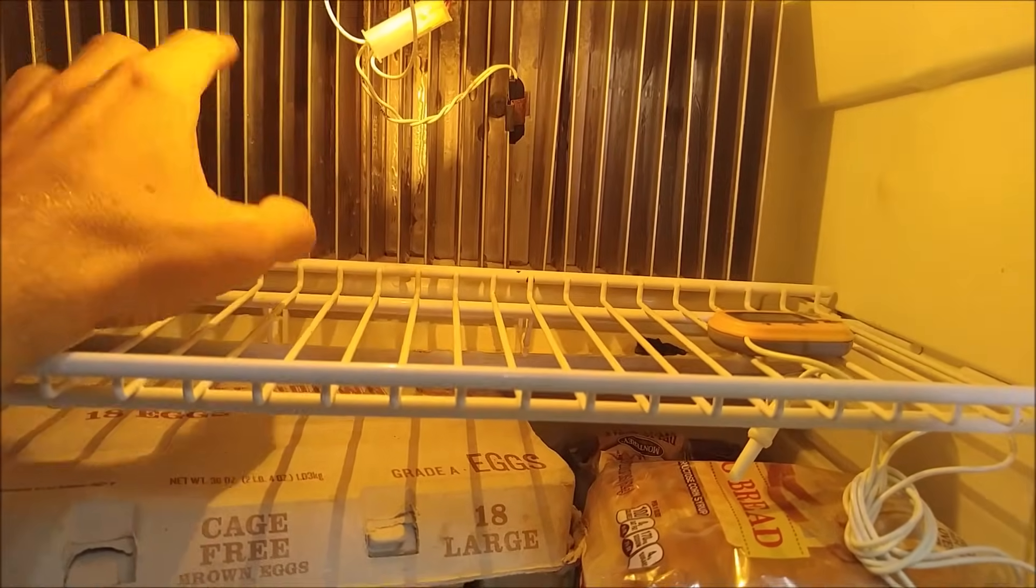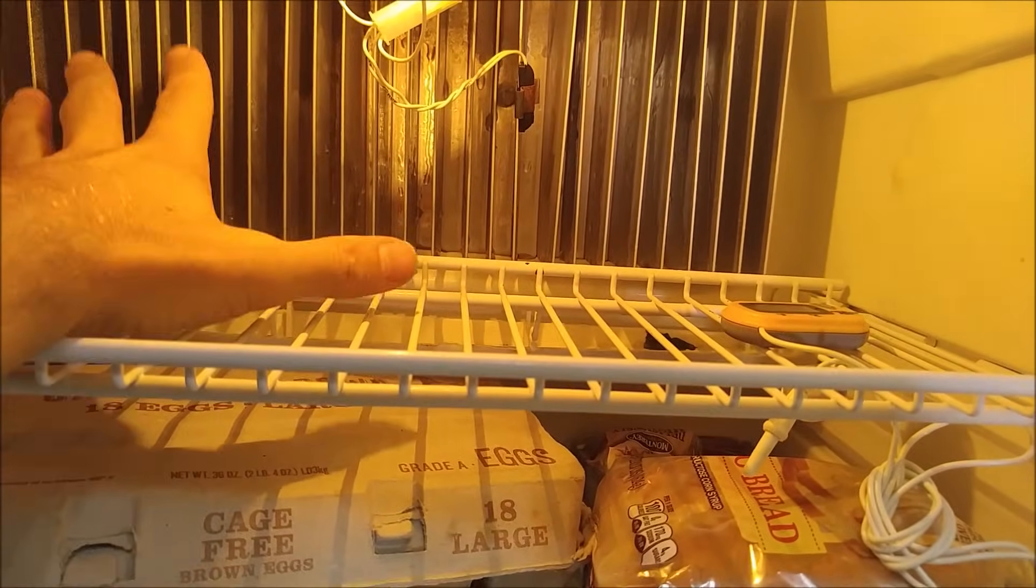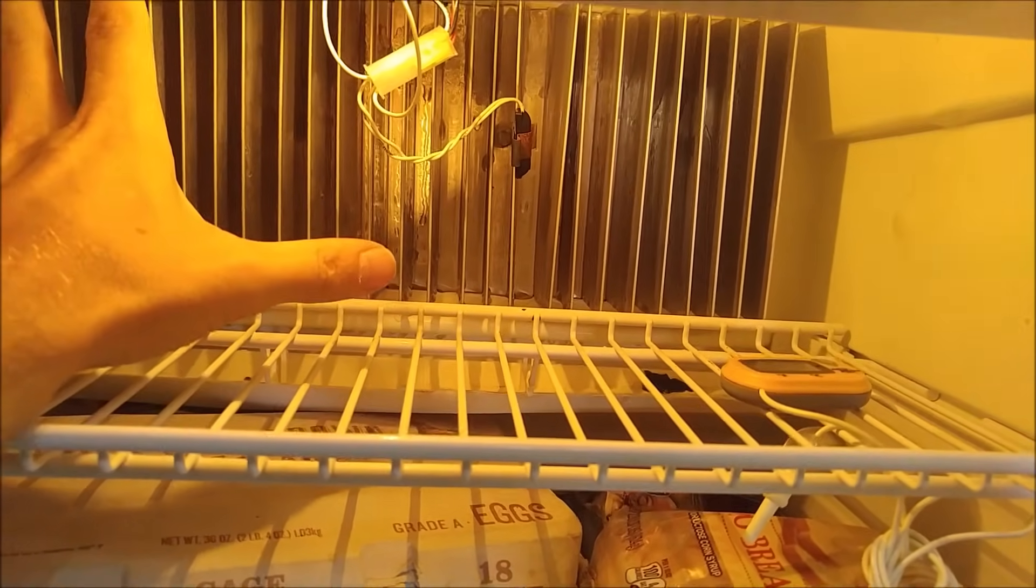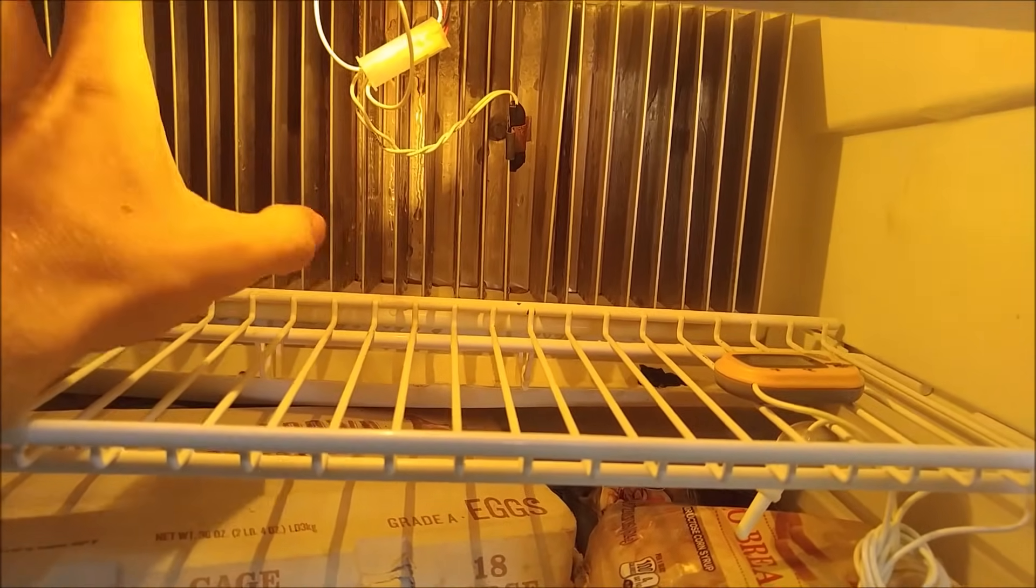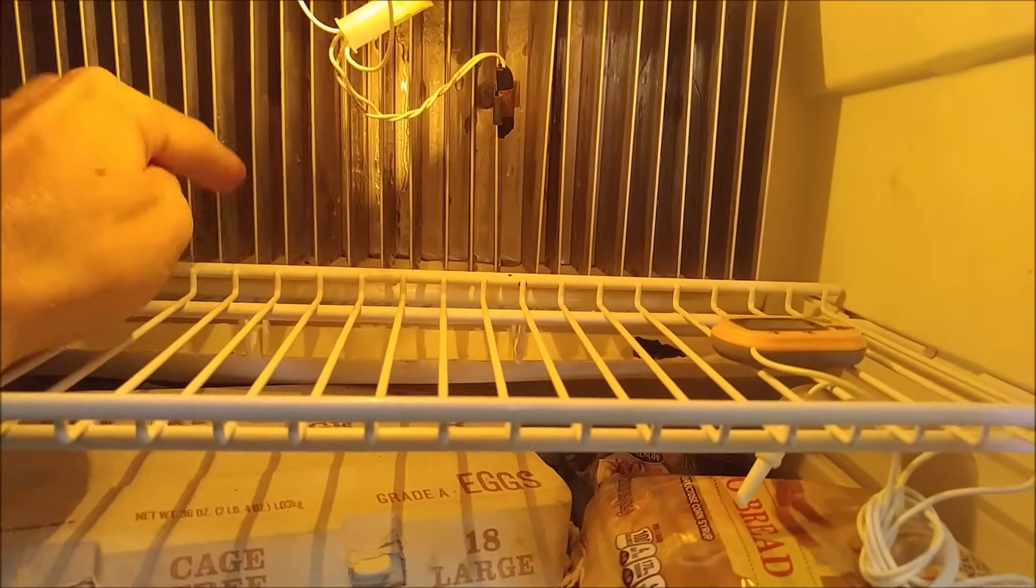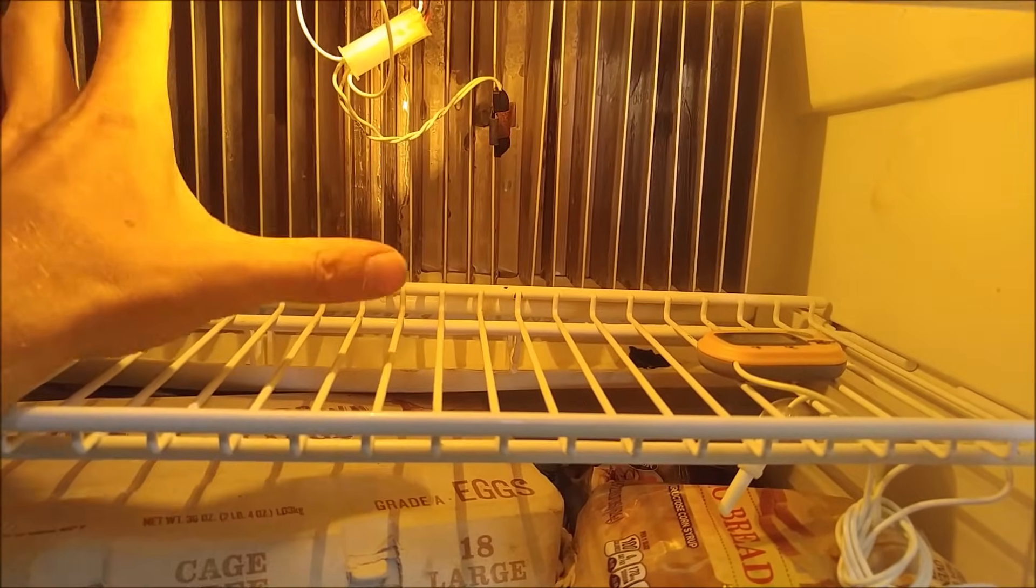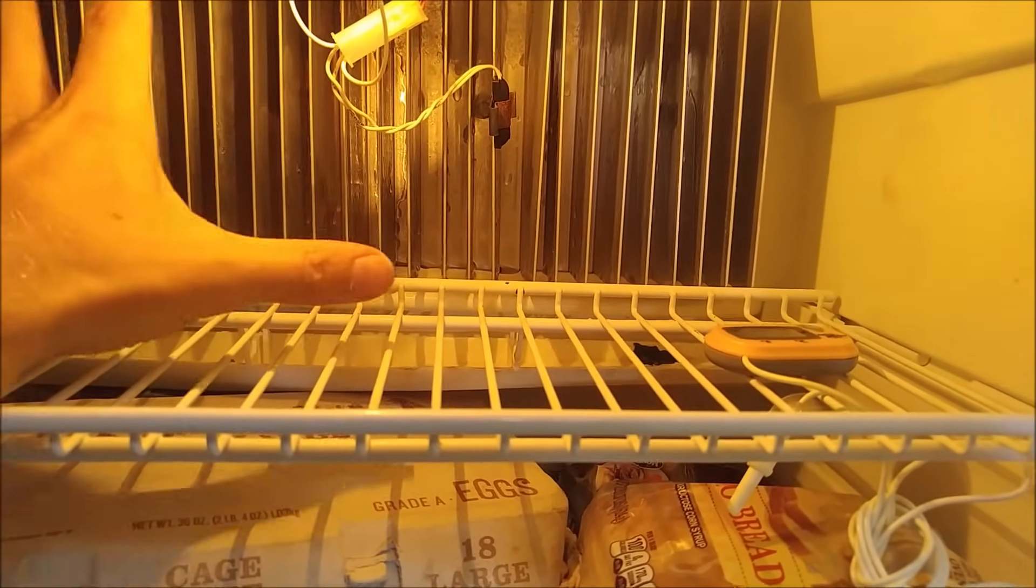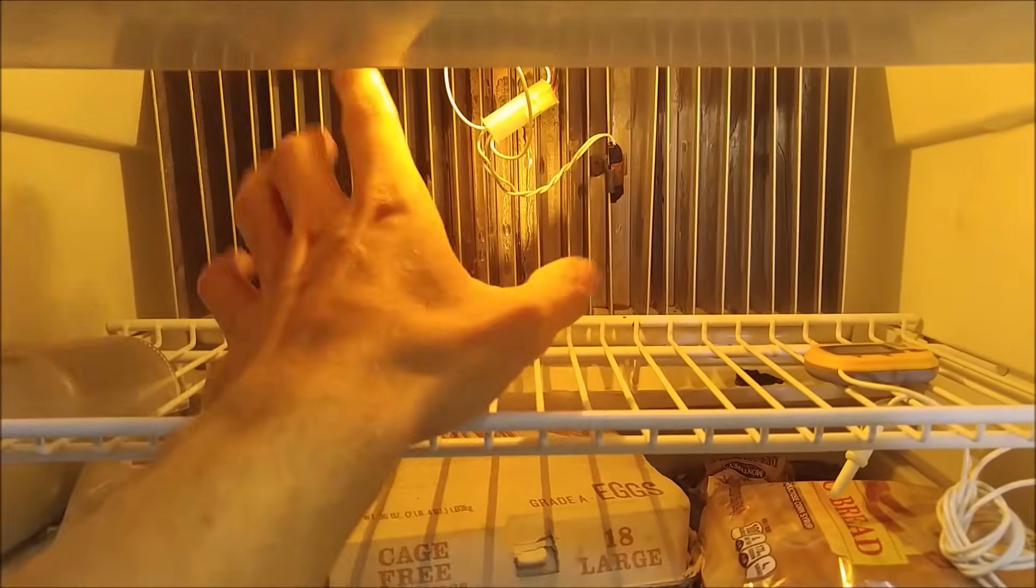It does have an auto-defrost feature and it automatically warms those up so that the frost melts off and goes down into the tray. If it's building up too much ice, you either have a door seal problem or you have a thermistor problem.